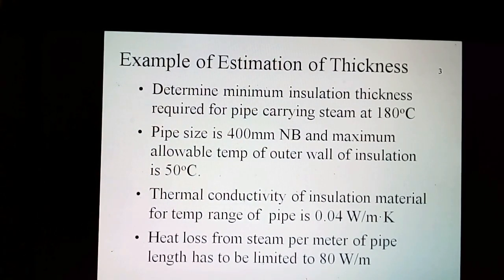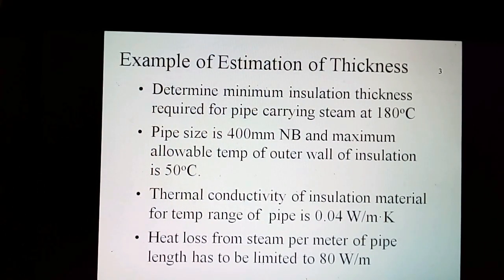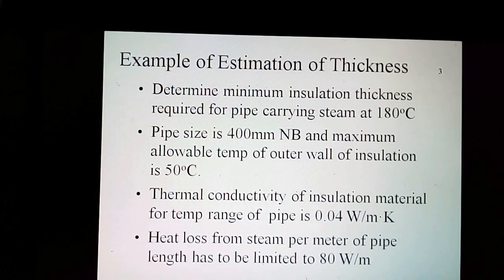Estimation of thickness for heat loss: Determine the minimum insulation thickness required for a pipe carrying steam at 180 degrees centigrade. The pipe size is 400 millimetres diameter, and the maximum allowable temperature at the outer surface of insulation is 50 degrees centigrade. Thermal conductivity of the insulation material is 0.04 W per meter per degree Kelvin. The heat loss of steam per meter of pipe length has to be limited to 80 W per meter.